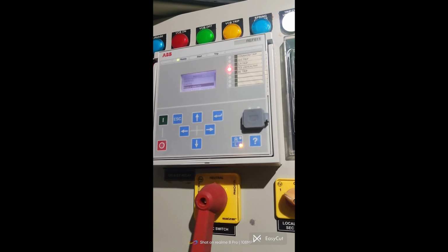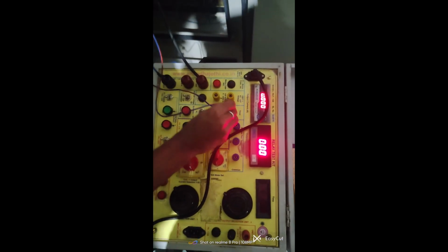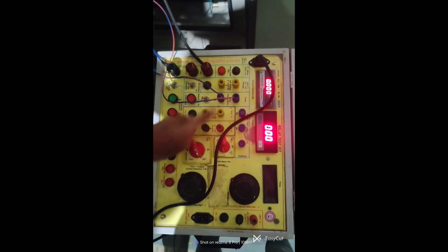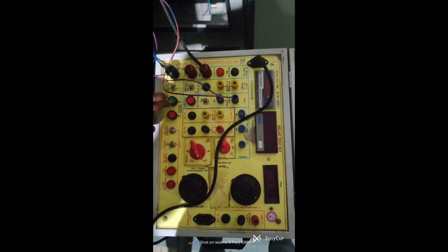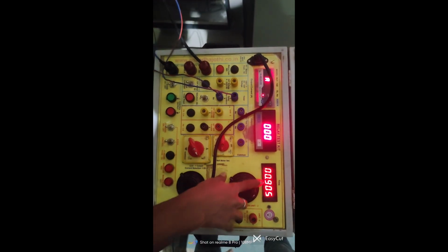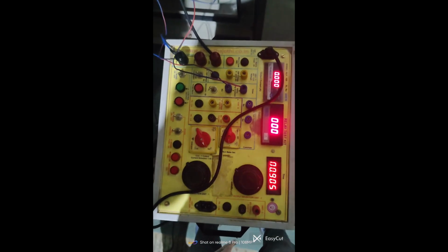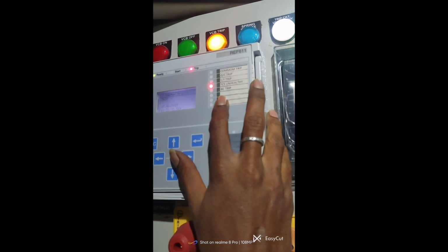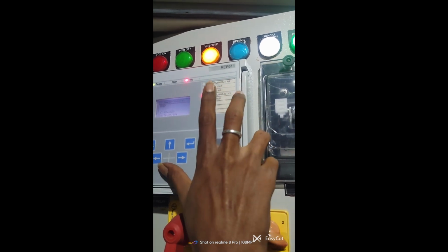Now the relay is in normal condition, no fault in this relay. The feedback cable is connected for our stop timing purpose. We can start the test. The relay trips at 0.9 second. The overcurrent and the common trip, the 86, is operated.